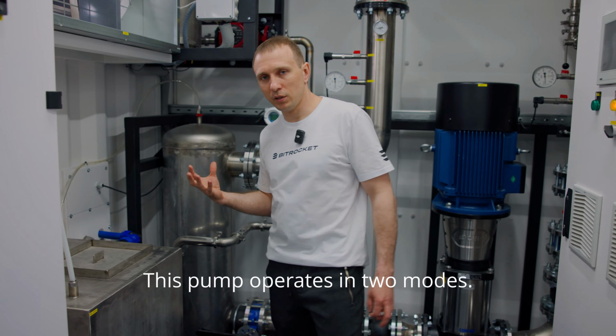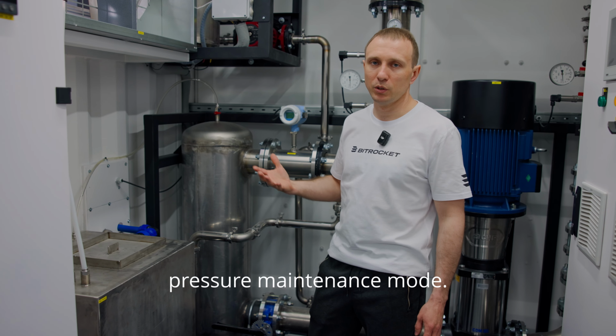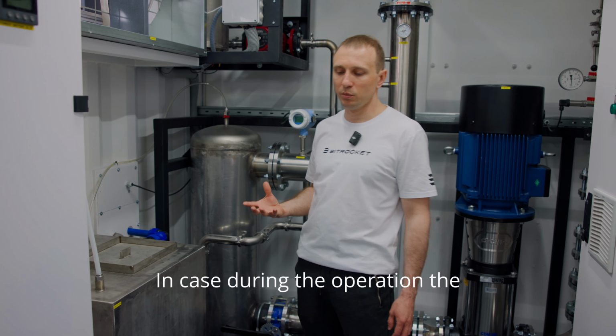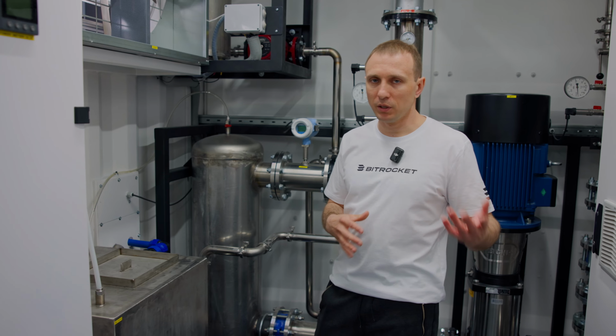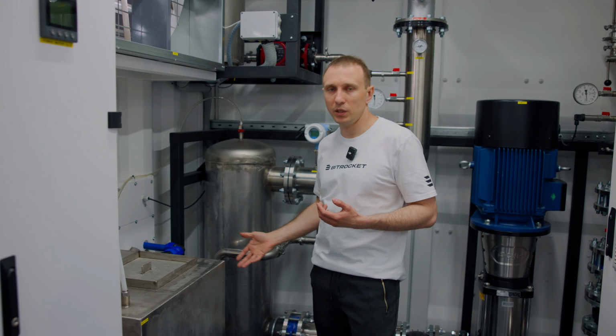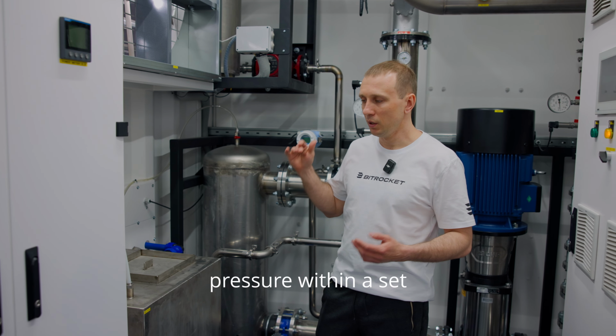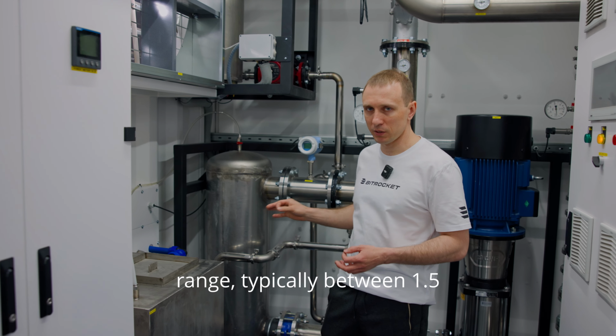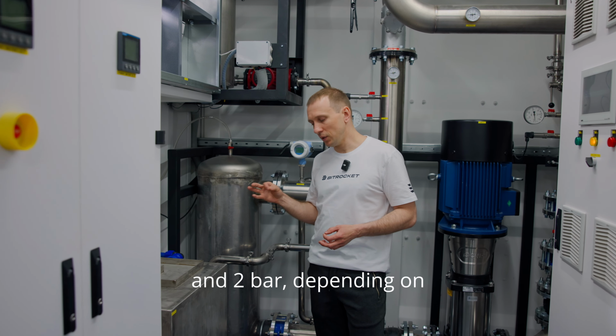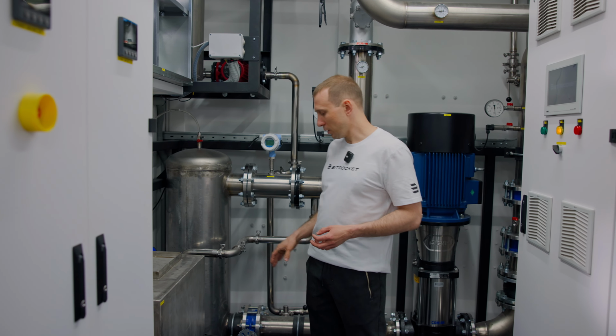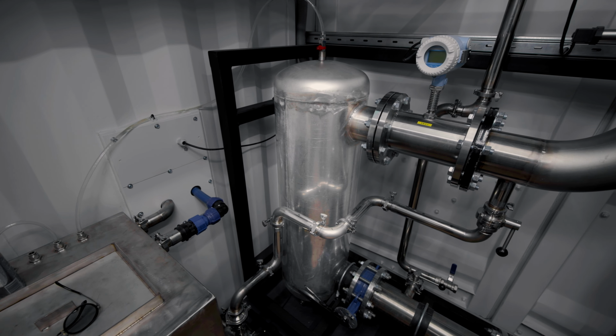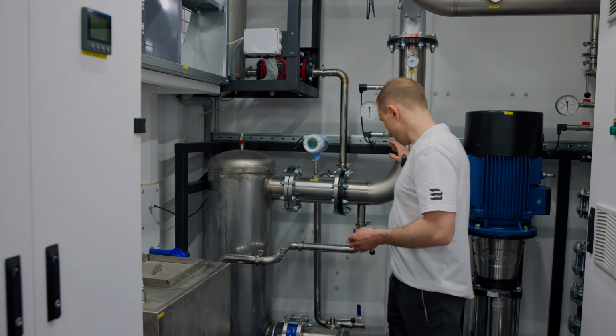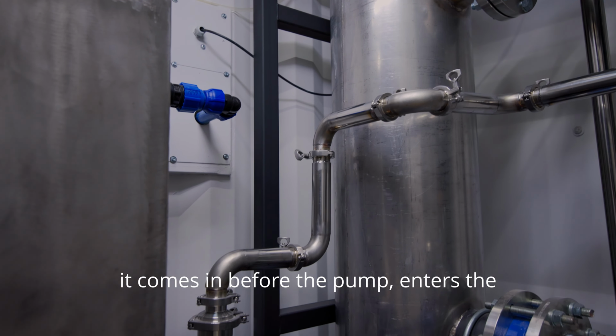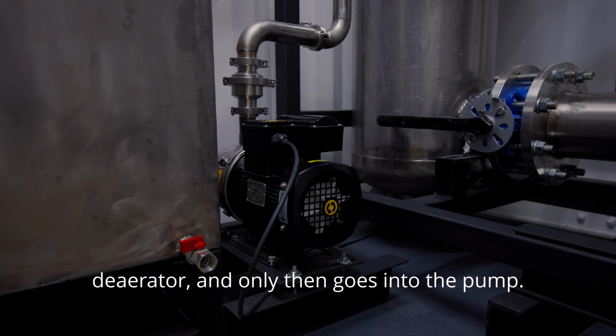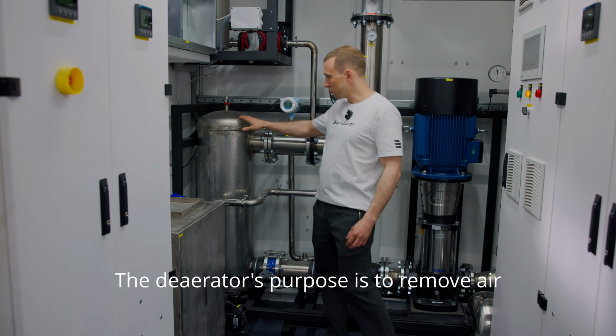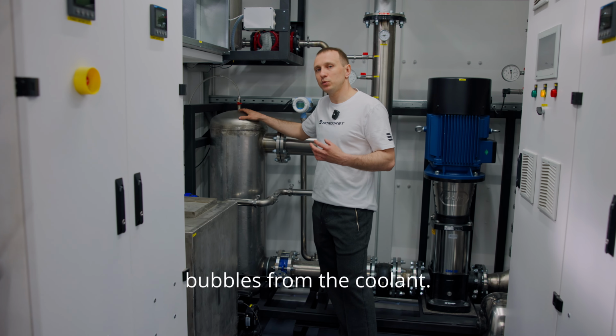This pump operates in 2 modes, the filling mode and the pressure maintenance mode. In case during the operation the temperature drops or rises, it works together with the safety relief valve. Its main task is to keep the system pressure within a set range, typically between 1.5 and 2 bar, depending on the specific configuration. The next component is the deaerator. The deaerator is installed at the pump inlet. This is the return line. It comes in before the pump, enters the deaerator, and only then goes into the pump. The deaerator's purpose is to remove air bubbles from the coolant.